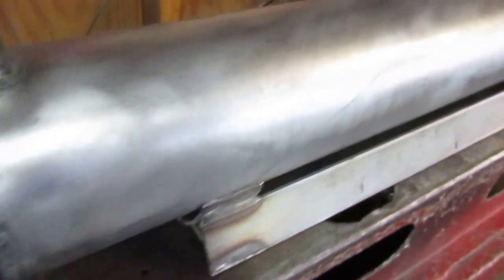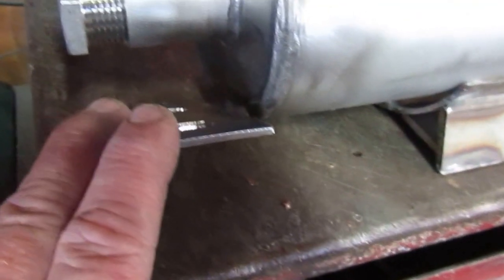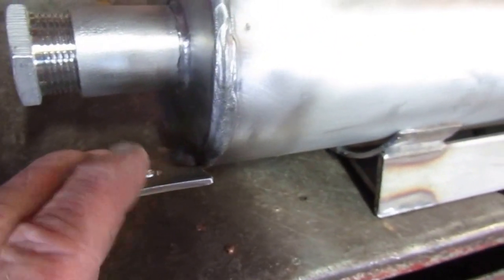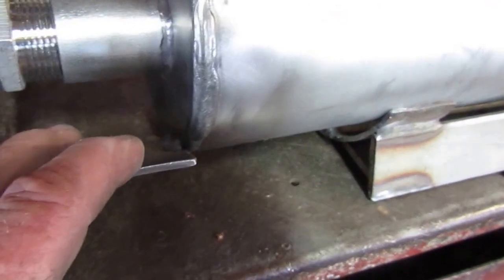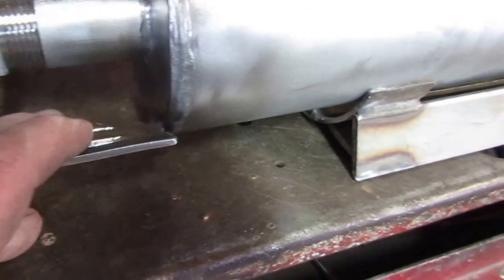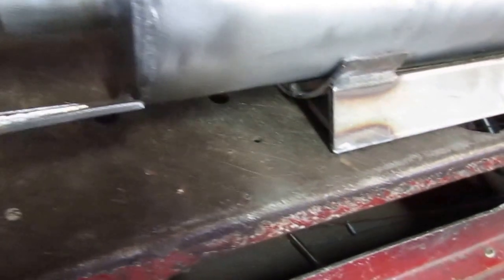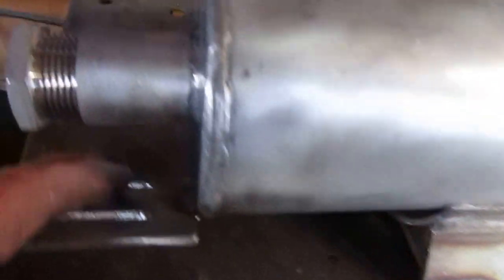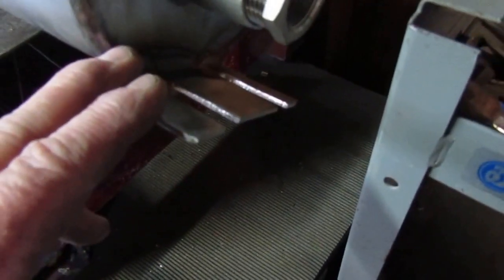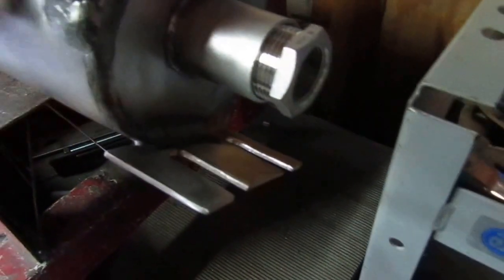Again, this is high pressure tubing, and we put brackets. In this case, this will go onto an L cradle type bracket, shelving bracket that comes off the recovery tank. And I open slotted it to allow a little bit of leeway there, to move it back and forth to allow adjusting, to retrofit the shelf bracket.